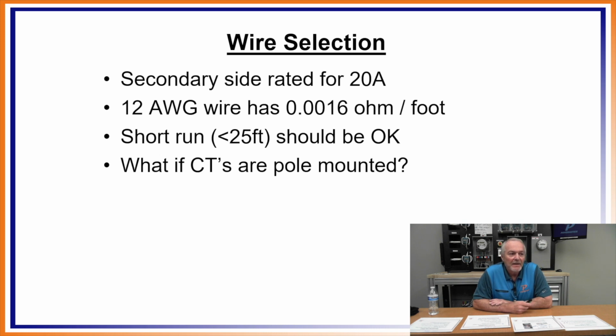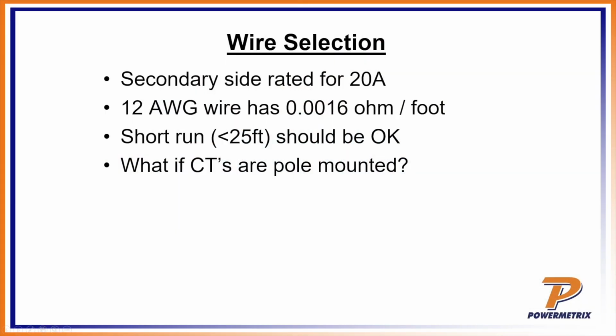So now wire selection. If I have a secondary side rated for 20 amps, and I've got number 12 wire there, you see how much resistance there is per foot with this wire. Hence what we talked about earlier about going from 14 to 12 to 10, right? So if you run a short run, remember it's per foot. There's a resistance per foot in wire. So the farther I get, the more resistance I've added. That's why earlier, with 50 foot of number 14, the farther I get away, the more resistance I'm adding, the more potential problems, because now I'm adding that burden, right? So you can see a short run of less than 25 feet, we should be okay, but what if the CTs are pole mounted? That's when you get into the extended distances. As we extend that distance, per foot, we add the resistance in there, okay?